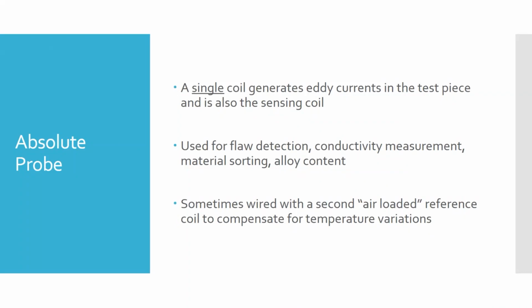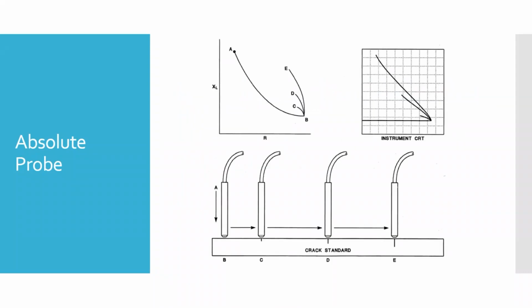Some probes are wired with a second air-loaded reference coil, because in addition to the metal in front of a coil, coils can be affected by air temperature. So even a simple absolute probe with a single measurement coil may have a second coil inside it to compensate for those temperature changes.